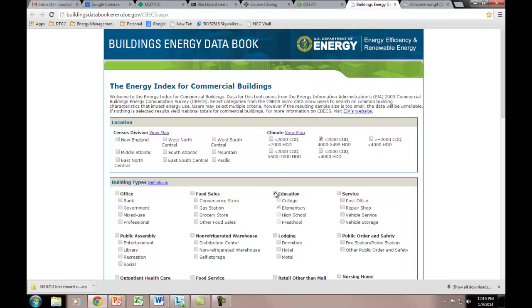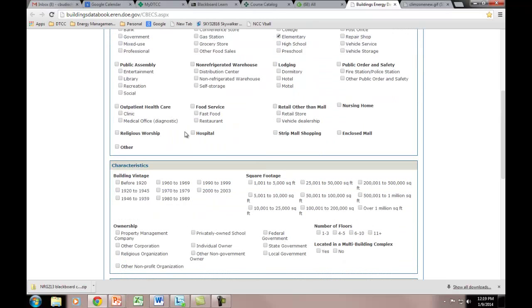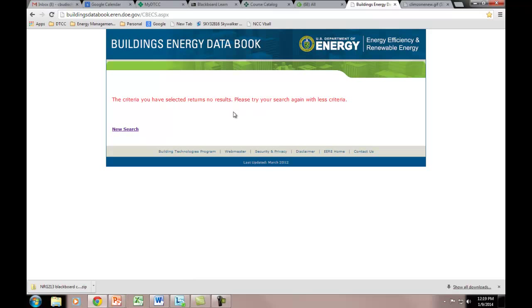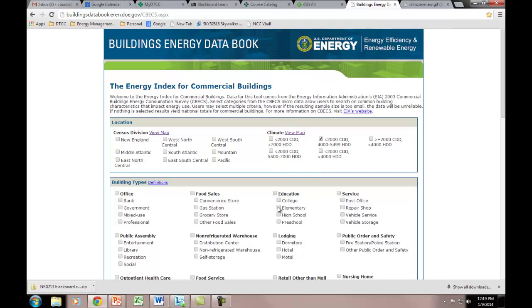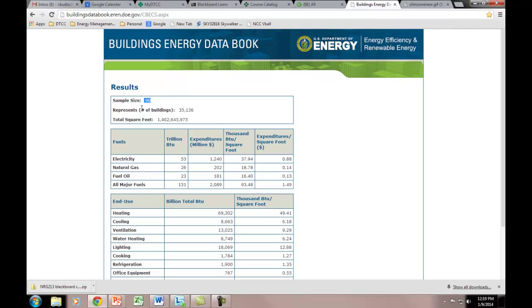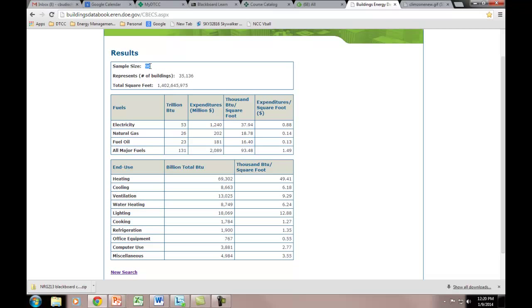Let's say yours is an elementary school — we can select elementary school. You might know the square footage of your building, so you can narrow it down that way. But when you're really specific, your criteria can have no results. So let's go back and do a new search with the same cooling degree days but just select educational building. Now this gives a sample size of 90 buildings. We can see thousands BTU per square foot — that's the EUI — and expenditures per square foot, which is the ECI. Use the bottom numbers because that's the total for all fuels. Be careful: if your sample size is less than 25, you're not going to get good results, so make sure the sample size is more than 25.